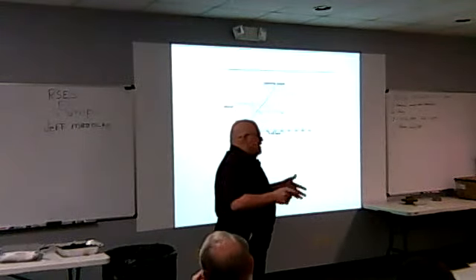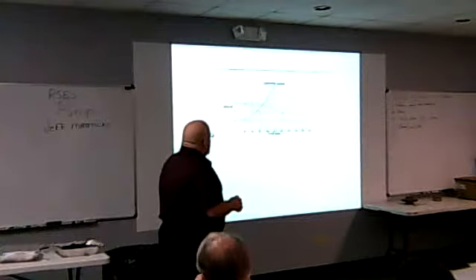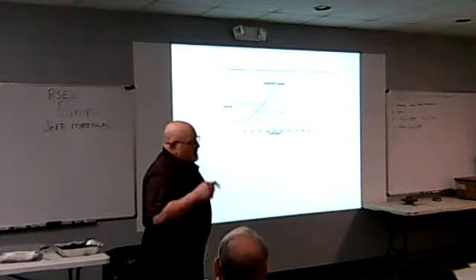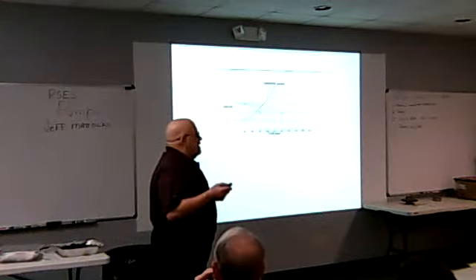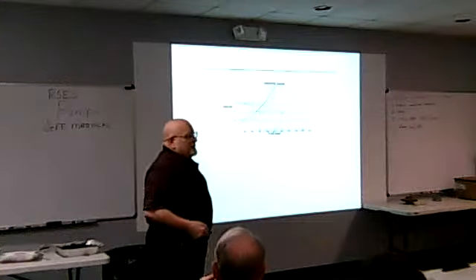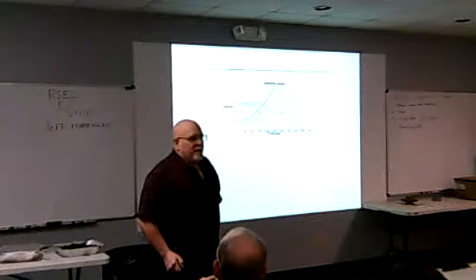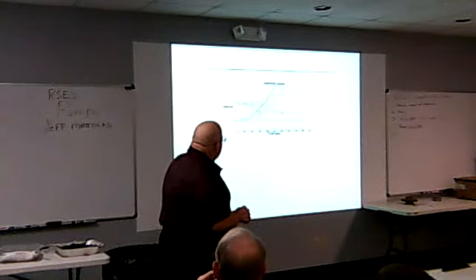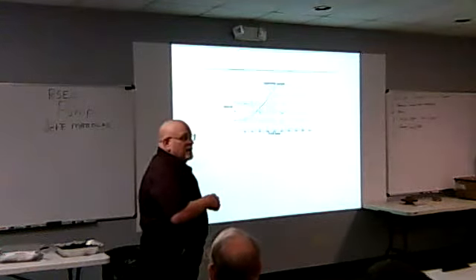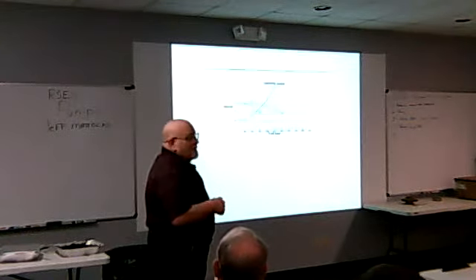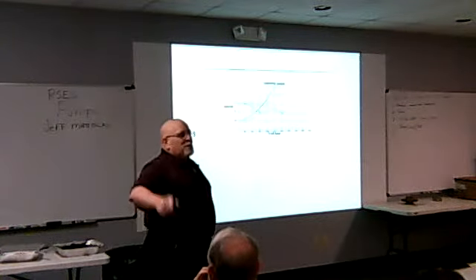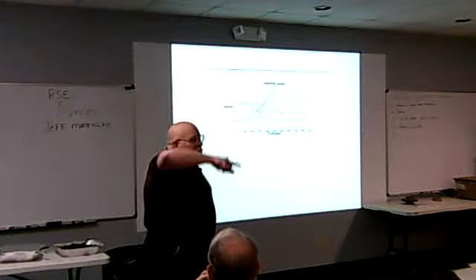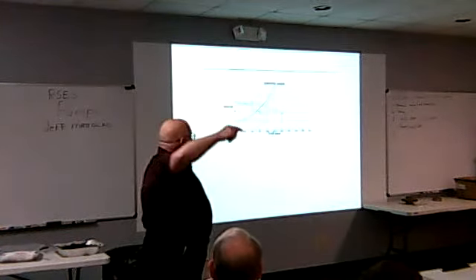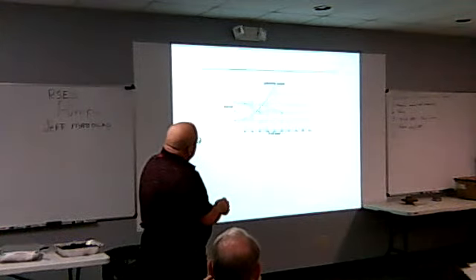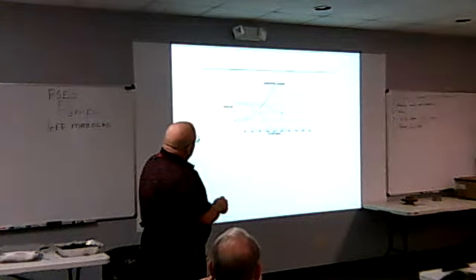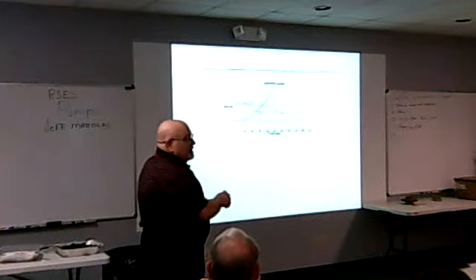But when you make a pump selection in parallel, a lot of people think, I wrote an article for Plumbing Engineering quite a few years ago. People always say, well, I need more flow, let's just put another pump in. Well, it doesn't work that way, because the head varies as the square of the flow, remember? So if I double my flow, what's going to happen to my head? It's going to go up by the square. The pump no longer has enough head. So if I make this selection, this is my original pump. Right here was my selection. Here's my system curve I laid in.